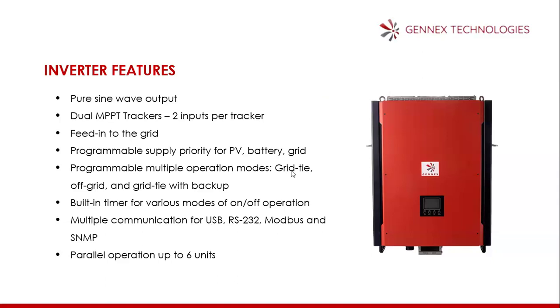It has a built-in timer for various modes of on and off operation. So if maybe you want it to charge for a particular time, you can program it. If you go through the manual, you see how all these are set. There are multiple communication ports, USB, RS, all on the body of the inverter. You can communicate through SNMP, so that communication could go through the internet, which means you can monitor the inverter online as well.